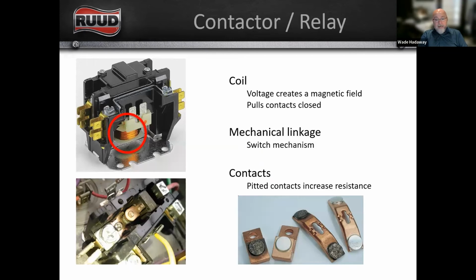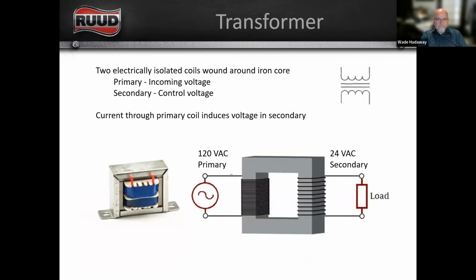A lot of times that is caused by not having enough voltage at your coil, right? So if you've got chattering contacts, you could have undersized low voltage wiring. You could have a voltage drop somewhere because you've got a wire nut that's really not very good, or you've got some other sort of voltage drop. We'll talk about that a little bit more here in just a second.